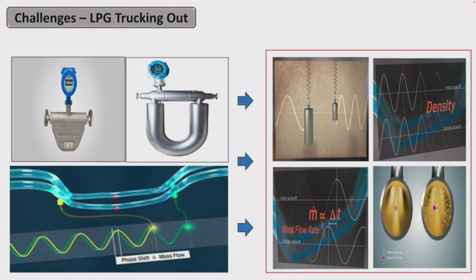Normally, in normal operations, when you don't have any movement, it's stable. But when you have product going through this flow meter, there's a twist. So the difference between these twists is directly proportional to your mass flow that is passing through the Coriolis, as you can see from there. For your density, normally, if you have a denser product, the frequency of the oscillation is reduced, and that also determines the density.